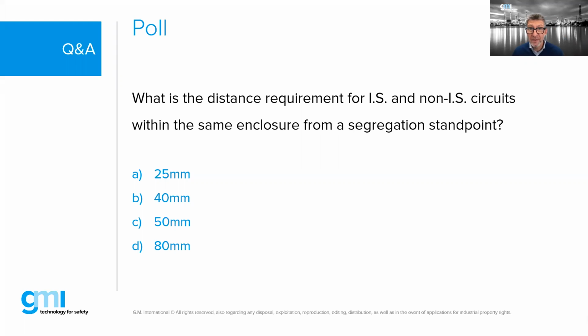The poll results are mixed, but the correct answer is C: 50 millimeters, or 2 inches—that's the required separation distance between IS and non-IS circuits. Sharing the results now: some said 50, some 40, some 25. 25 is too short, not enough.